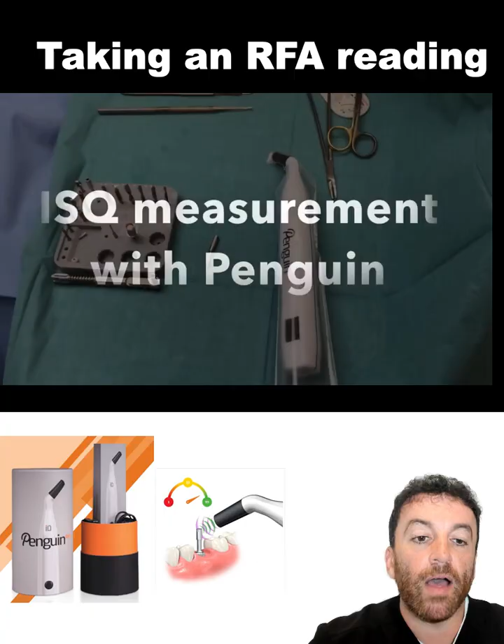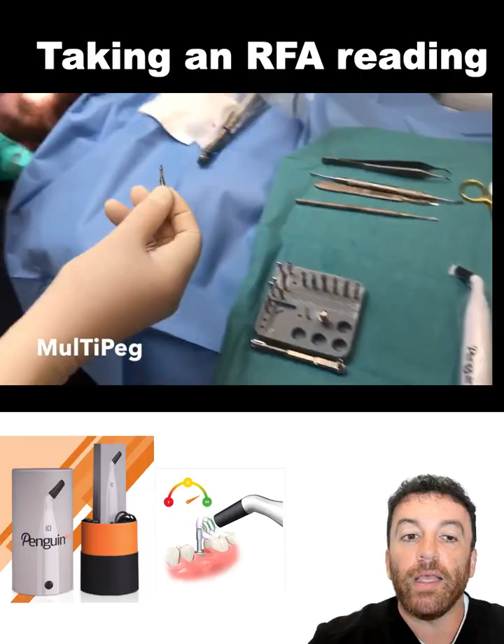How do we measure lateral stability of the implant? That's where the devices such as the Penguin or the Osstell units come into play. So at the time of placement of the implant, you can take a measurement, and then at 2 or 3 months later, you can retake that same measurement. Now you have objective readings that you can verify. And if you find that the trend is increasing in values, that's a positive.